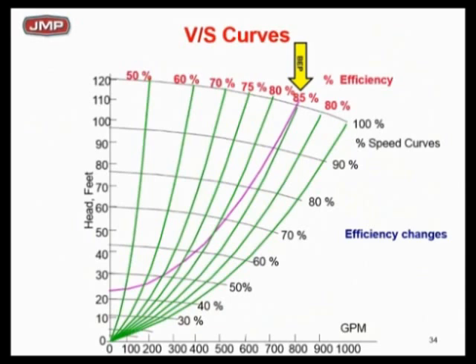Let's go deeper. What would happen if my minimum control head was 25 feet — like this purple line? In the real world, as I slow the flow down and slow the speed down, I'm not following the 85% BEP green line all the way down. I'm following that purple line, because at zero flow I've got to have 25 feet of head. It looks like I need to be running at about 45% speed, and I've just crossed over the 50% efficiency line — when you thought you were at 85%.